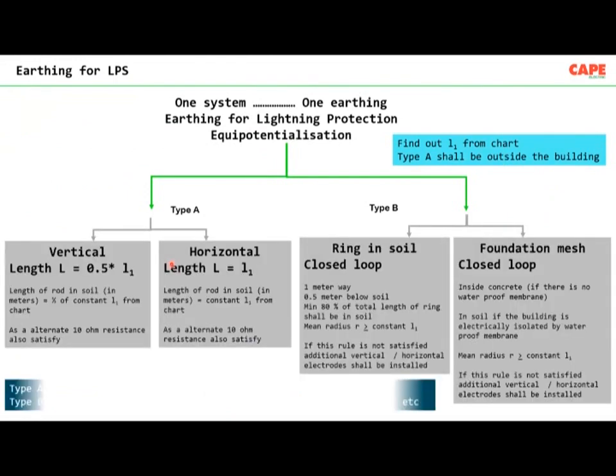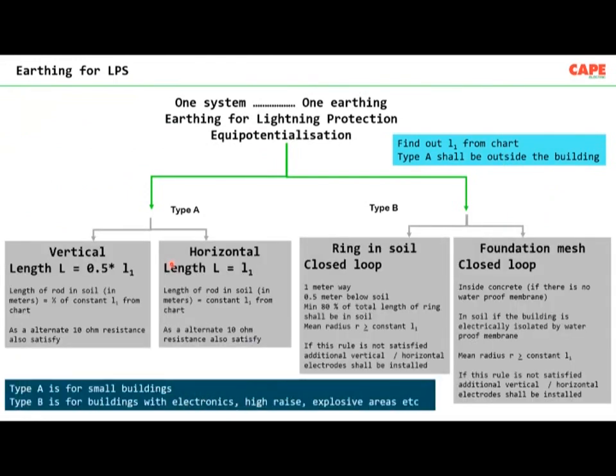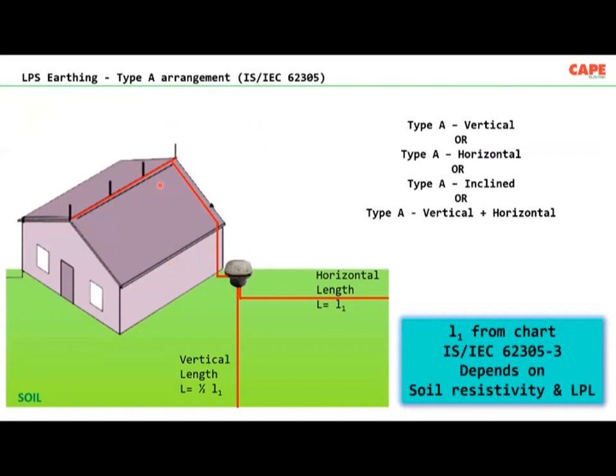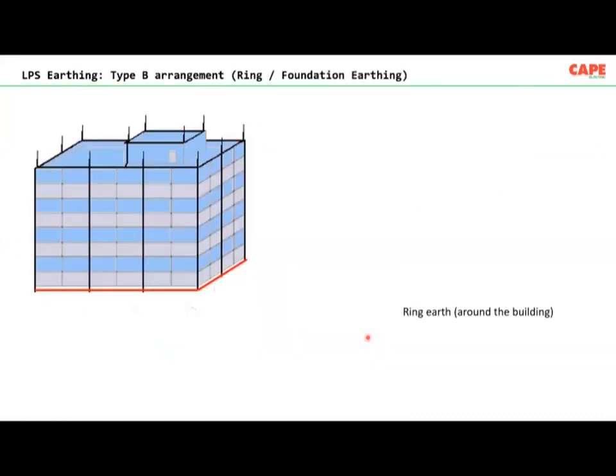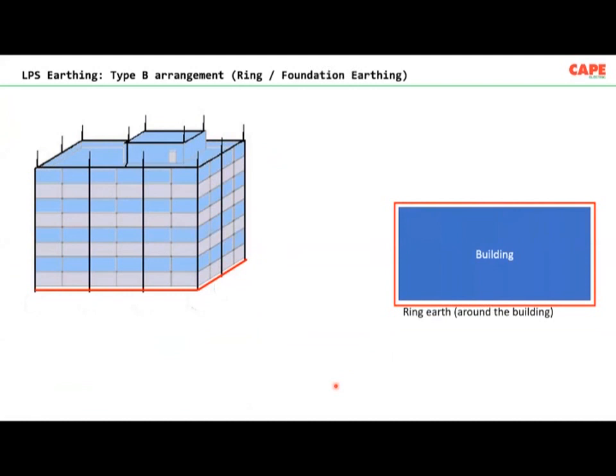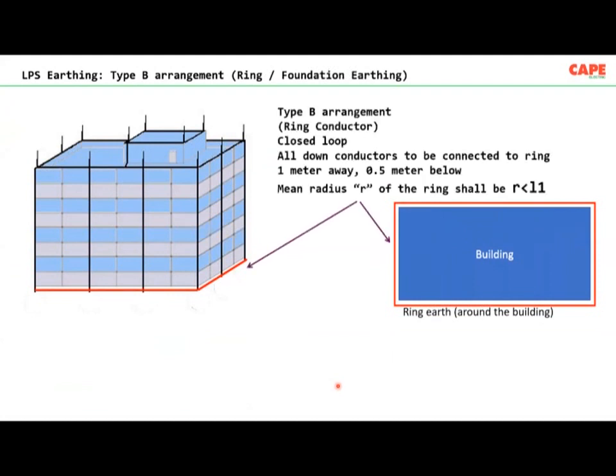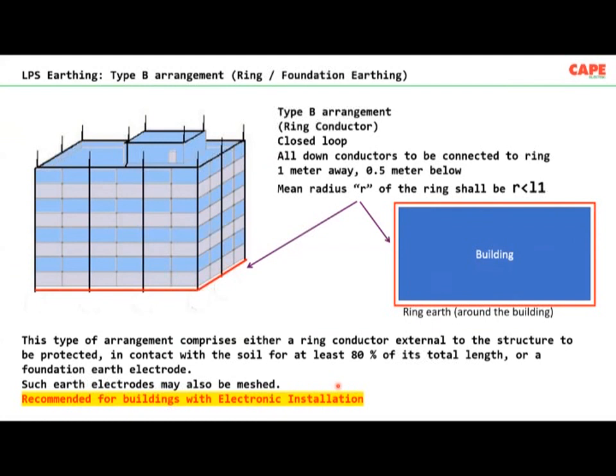Now, earthing of lightning protection is carried out in two ways, type A and type B. Type A means for every down conductor, you have to have either a vertical conductor or a horizontal conductor. This is called type A. Type A is recommended for smaller buildings. For larger buildings and larger industrial installations, we are supposed to have a ring conductor. Type B means a ring conductor all around the building, 1 meter away from the building, half a meter below soil, as a closed loop. This is the best way of dissipating lightning current in existing buildings.